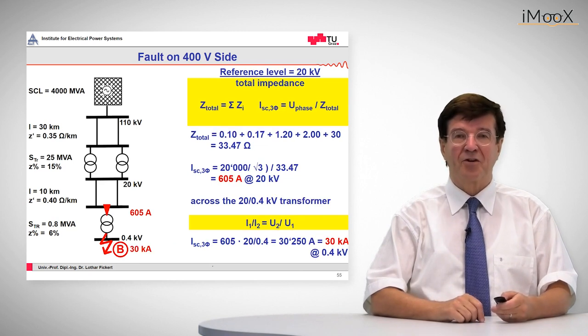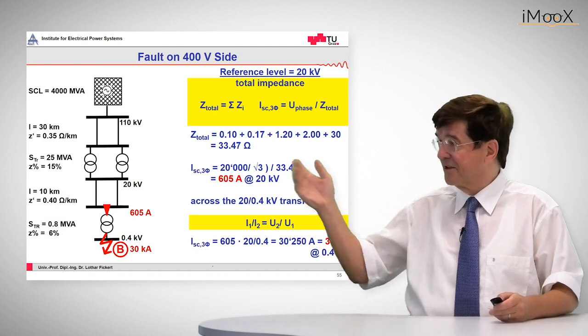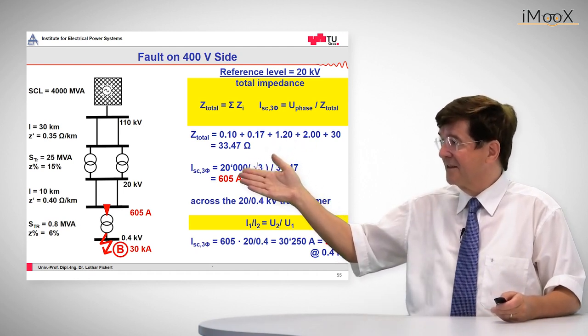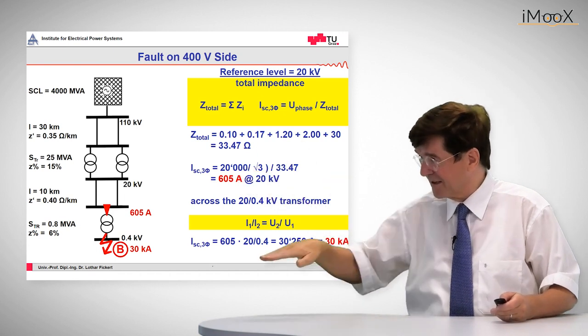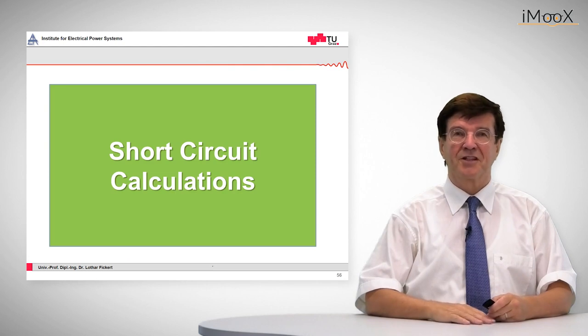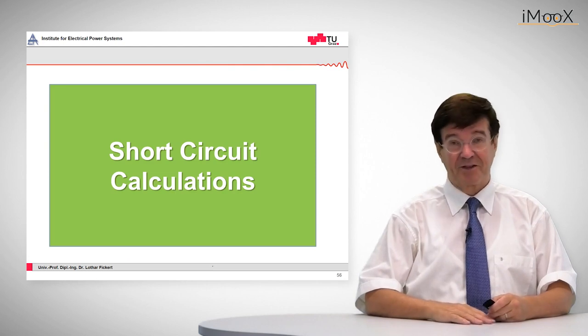So the total result is given in this picture: 605 amps on the high voltage side of this ring main unit transformer, 30 kA at the low voltage side, and that was the chapter about short circuit calculations. Thank you very much.